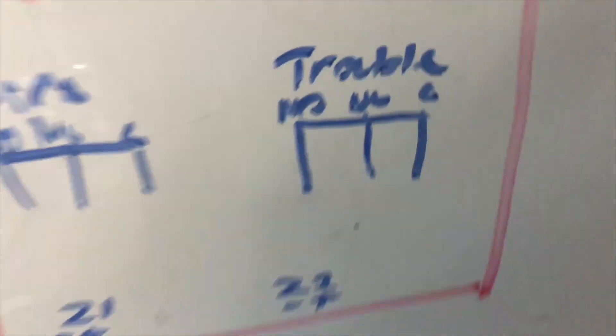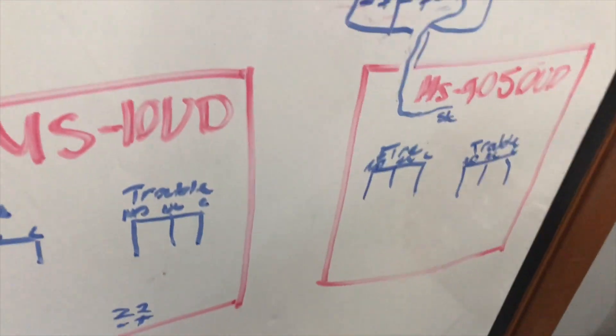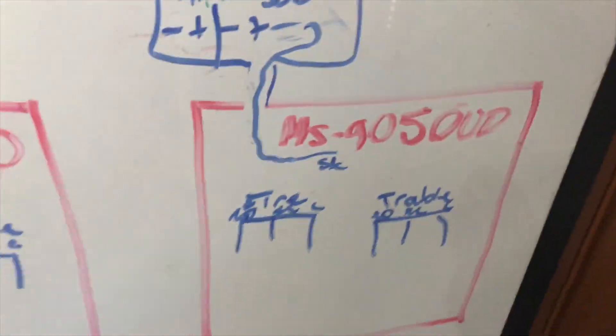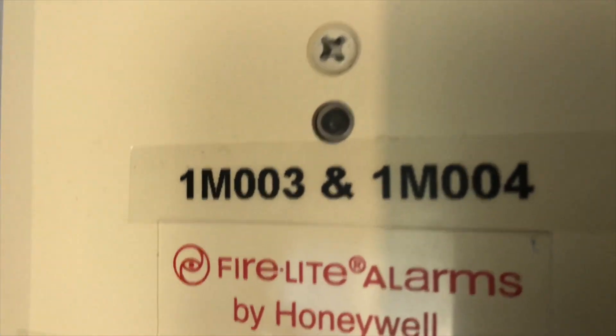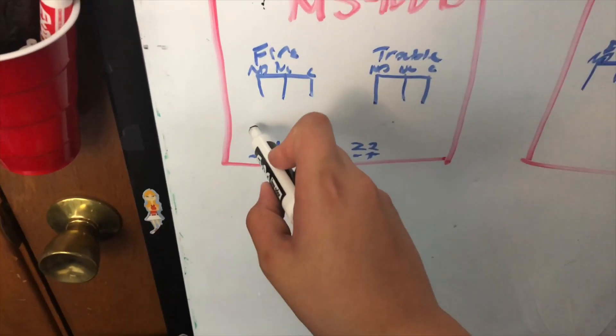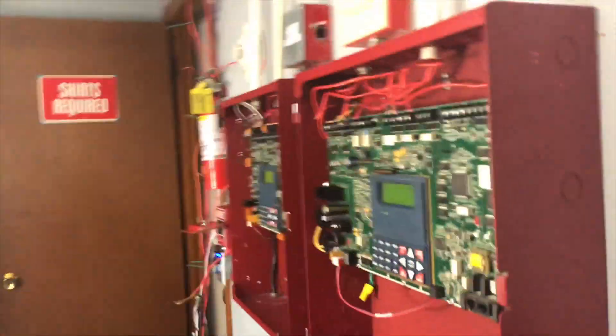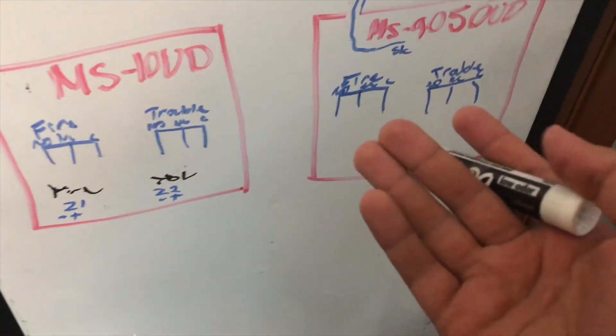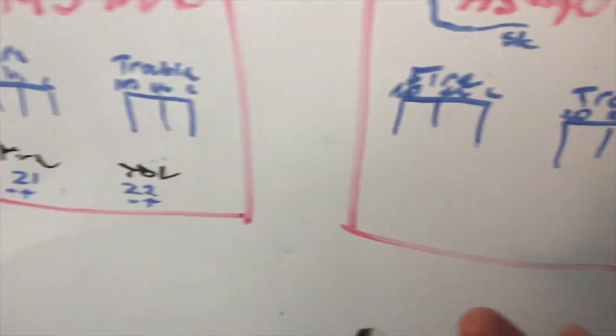I'm going to go over here to my diagram. The MS-10UD has fire and trouble relays, and zone 1 and zone 2 are what I'll be using for the demonstration. The 9050UD is addressable, so we have an SLC in addition to zones. There's a dual monitor module, so you can see it double-polling for each two addresses — two zones basically. We also have fire and trouble relays here. One zone will be set to a fire type and the other to a trouble — specifically supervisory — so they won't activate one another during the demonstration.